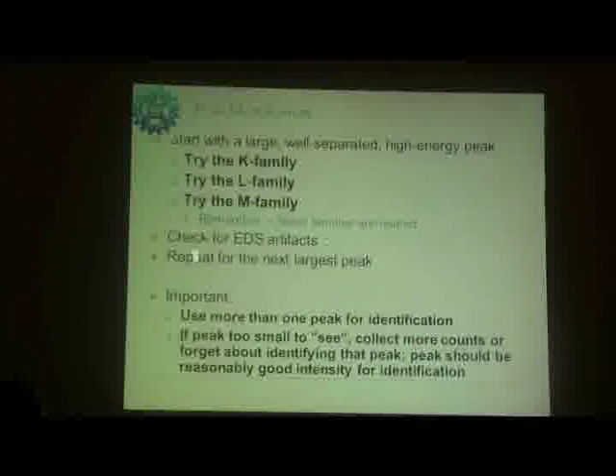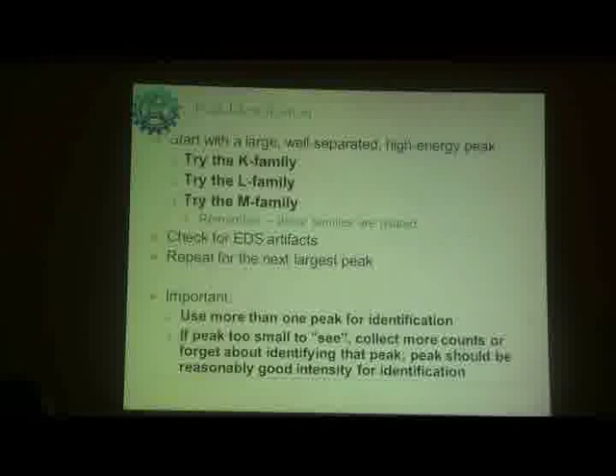So you have to start with a large, well-separated, high energy peak, try the K family, L family, and M family. So these families are related. Check for EDS artifacts, repeat for the next largest peak. Use more than one peak for identification. If a peak is too small to see, collect more counts. Suppose you have a very small peak, you can collect more counts so that you get the peak intensity properly and reasonably good for identification.